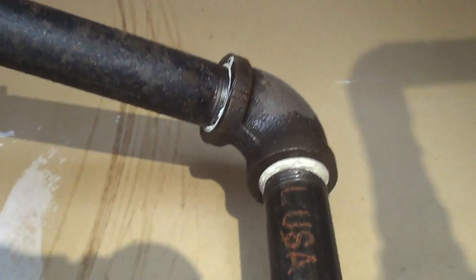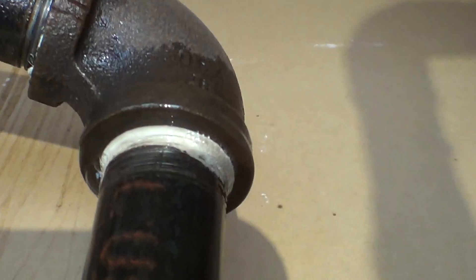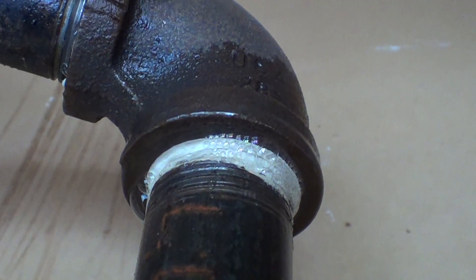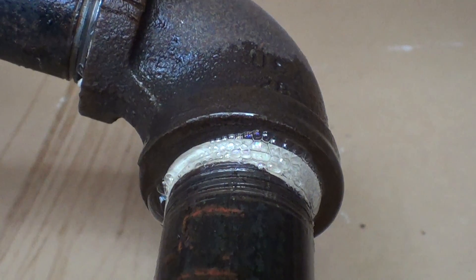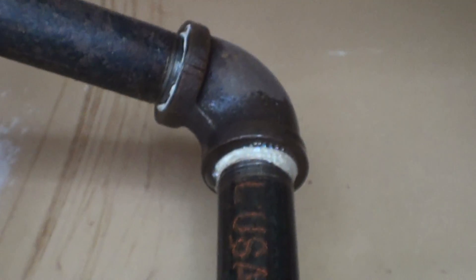I've got a couple gas leaks here that I can smell. So here's what a leak will look like. You see I squeezed it on, and then the bubbles will form. You can easily see the bubbles growing, but you didn't spray the bubbles on like a lot of the spray ones do.